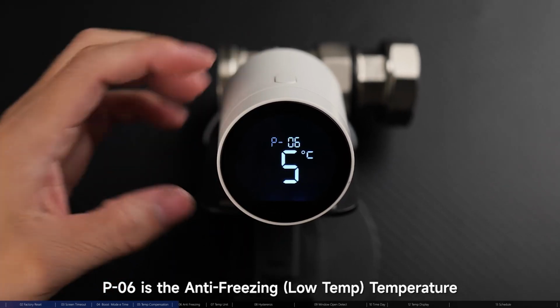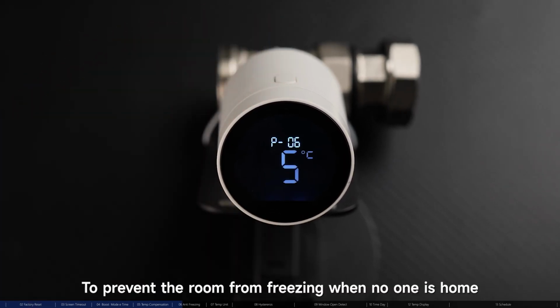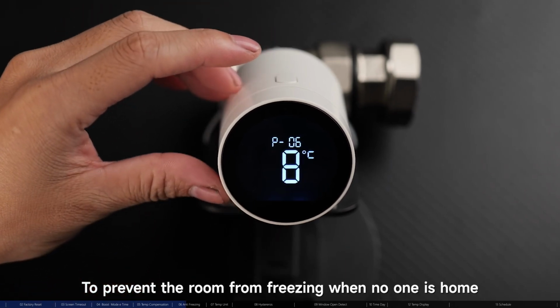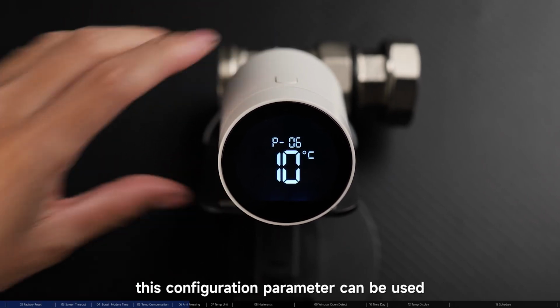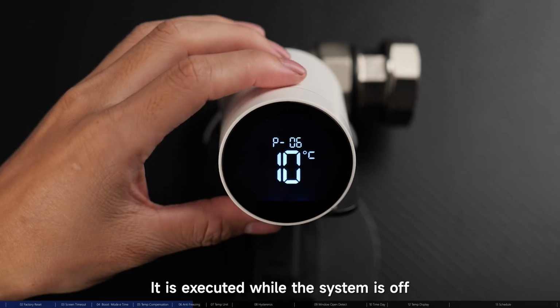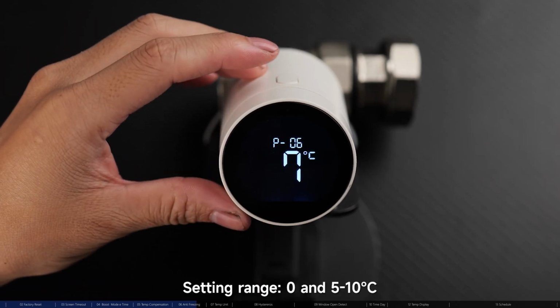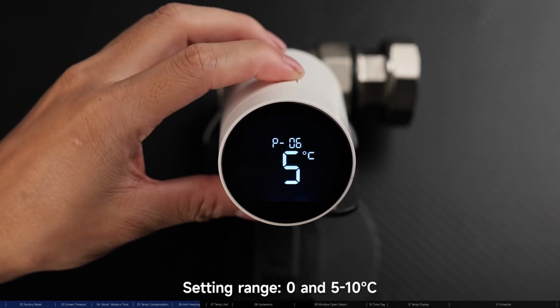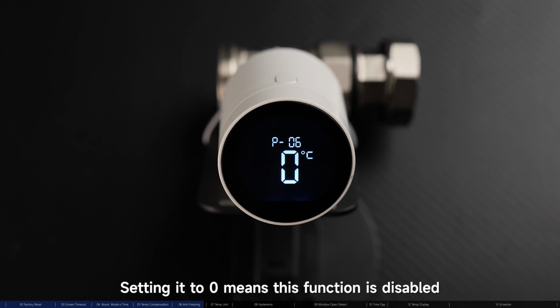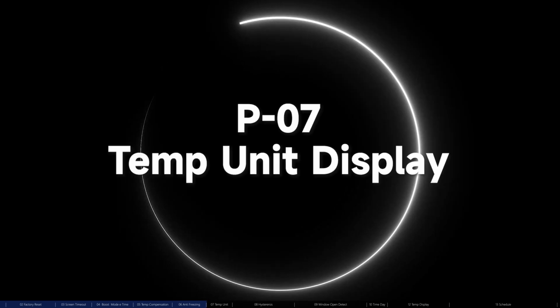P06 is the anti-freezing low temp temperature. To prevent the room from freezing when no one is home, this configuration parameter can be used. It is executed while the system is off. Setting range 0 and 5 to 10 degrees Celsius. Setting it to 0 means this function is disabled.